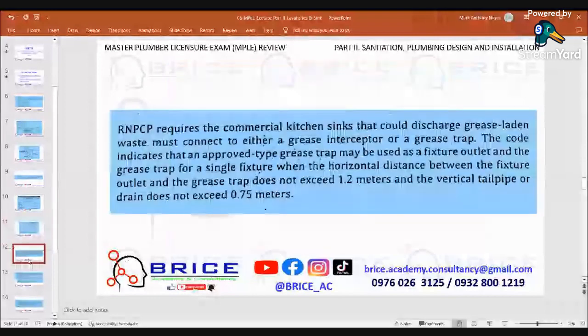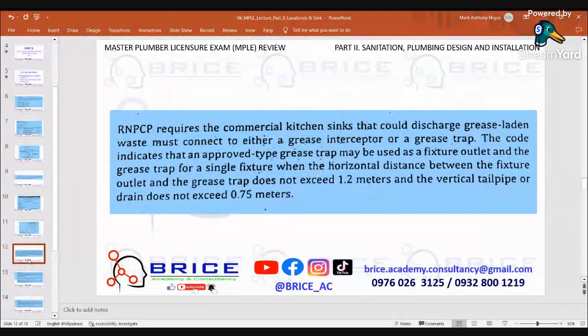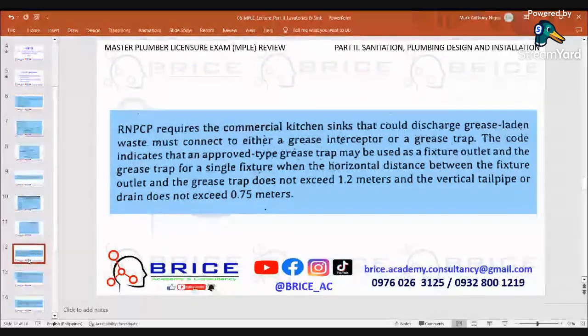The RNPCP requires that commercial sinks discharging grease-laden waste must connect to either a grease interceptor or a grease trap. An approved grease trap may be used for single fixtures when the horizontal distance between the fixture outlet and the grease trap does not exceed 1.2 meters, and the vertical tail pipe or drain does not exceed 0.75 meters.